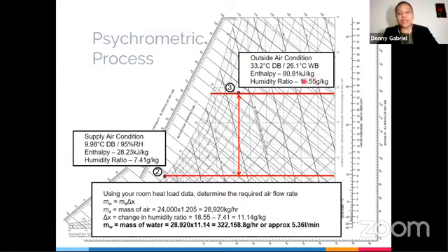This point is about 18.55 grams of water per kilogram of air. So for our 0.2, the 9.98, when you project your line, you will get also 7.41 grams of water per kilogram. This change in humidity ratio gives you the amount of water coming out from your equipment. Previously we calculated 24,000 cubic meter per hour. Using mass of water is equal to the mass of air times the change in humidity ratio, our mass of air, 24,000 cubic meter per hour, is changed to kilogram per hour. And the change in humidity ratio, 18.55 minus 7.41, is equal to 11.14 gram per kilogram.